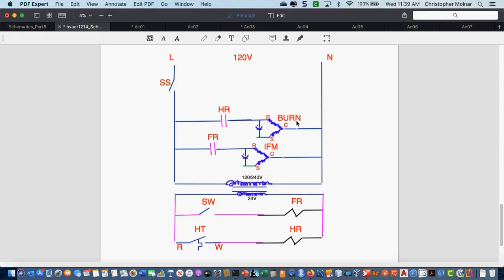Okay, so now, knowing that's my burner motor, what's my sequence of operation? Someone different give it a try this time. What's my sequence of operation? Anybody? Okay, anybody give it a try, please. Close the service switch, bring power to HR, FR on the transformer. At the transformer, go step down to 24 volts on a call for heat. Thermostat closes, power heating relay, closing HR, powering the burner. Close SW, powers FR, and powers the fan.